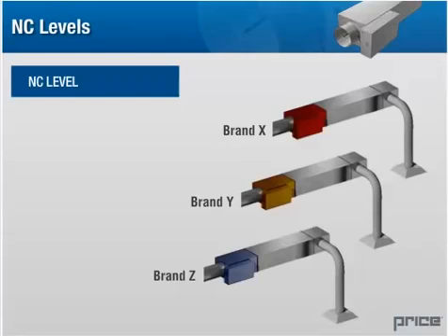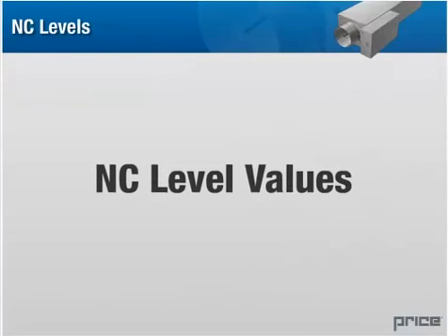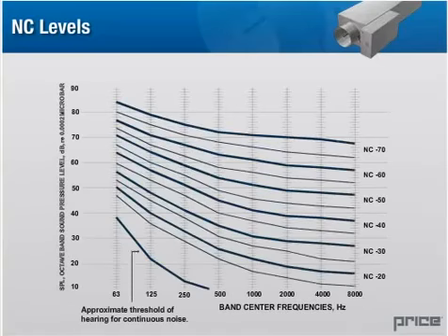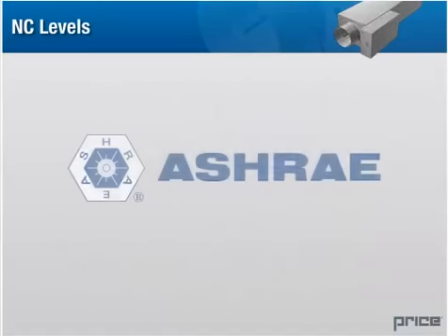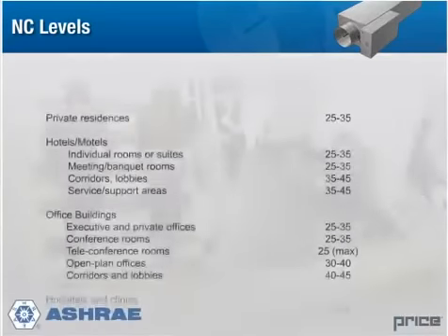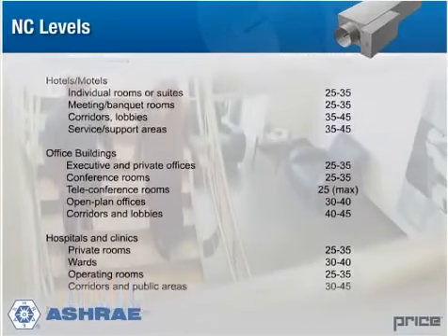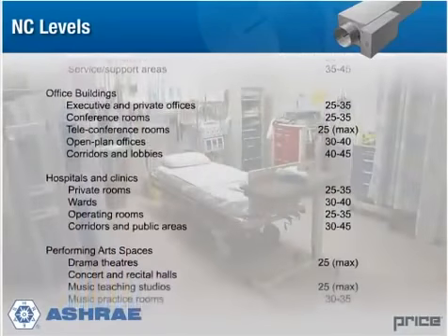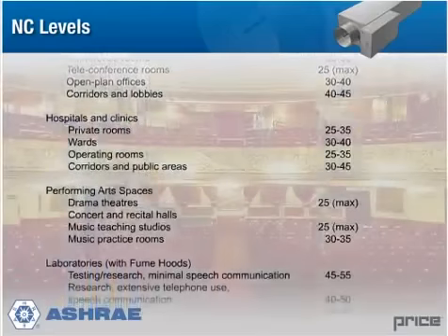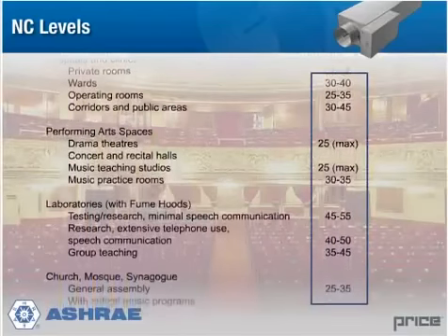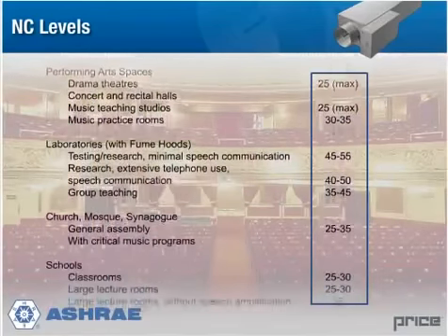Noise criteria, or NC level values, have become widely accepted as a measure of room noise levels and as a rating scale for equipment that is expected to stay within those levels. ASHRAE has issued recommended space NC values for many commercial air conditioning applications. These standards are used industry-wide. Terminal units should be selected so that the tabulated NC levels are within these designated standards.